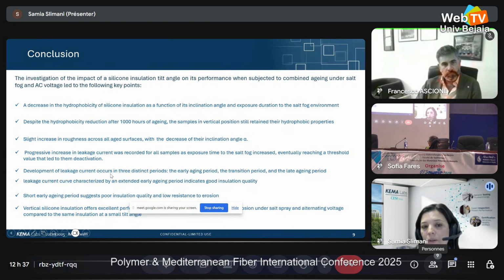Development of leakage current occurs in 3 distinct periods: the early aging period, the transition period, and the late aging period. A leakage current curve characterized by an extended early aging period indicates good insulation quality. A short early aging period suggests poor insulation quality and low resistance to erosion.